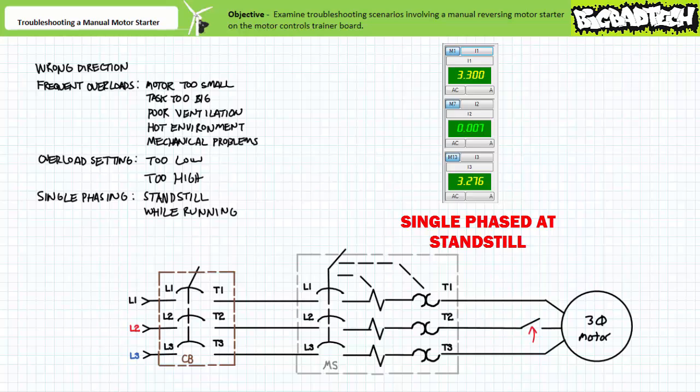Here's an amp clamp being used to measure line current of a three phase AC motor that's been single phased while at a standstill. Note current in L1 and L3 are way too high and L2 is carrying no current. Again, phase L2 is obviously the source of our problem.